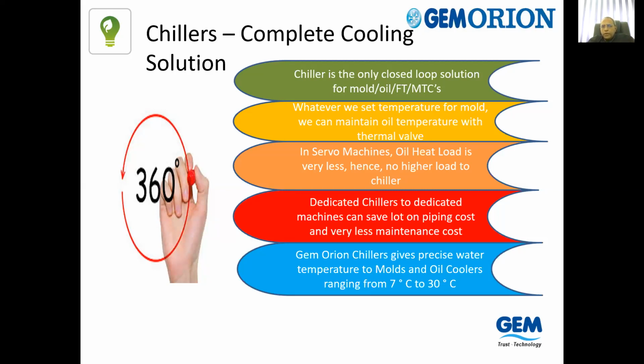So now the current trend, the Japanese method, is to use a dedicated chiller for dedicated machines to save on piping, and also the maintenance cost is reduced, because once this machine is operating, you operate the chiller, then you switch it off like that. So it is possible. Now, the advantage of the chiller is Orion chillers can give precise temperature, plus or minus 1 with our cyclic and plus or minus 0.1 with our inverter models, from any temperature from 7 degree up to 30 degree. Your set point can be anything.